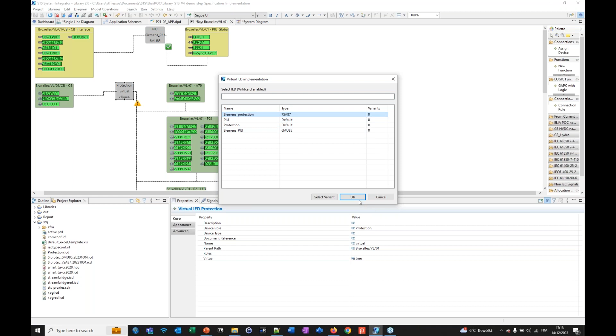When I implement my specification with a process ICD file, with an ID generated by a process ICD file, the tools will read the information, the IEC 61850 namespace information inside the process ICD file, and will automatically update it. You see, I don't know if you can see on the screen, but on each logical node here, if we are at the virtual step we have an open icon, and when it's implemented we now have a closed icon. That means this logical node is now implemented, with the information given by the process ICD file, given by the job done by Cedric just before.